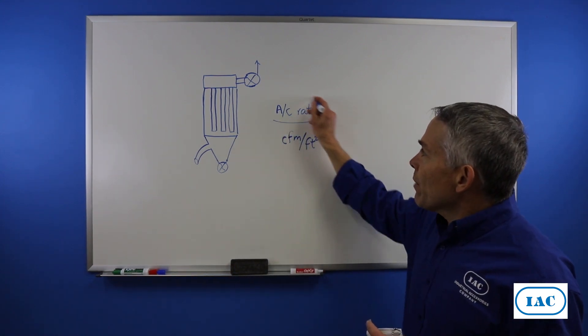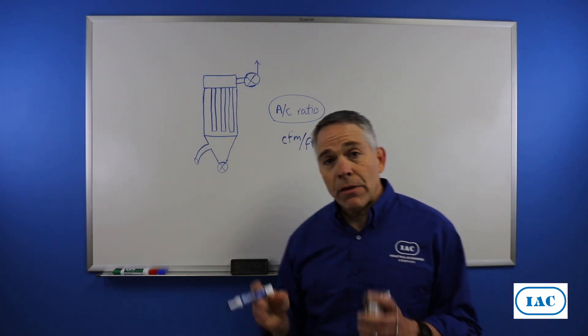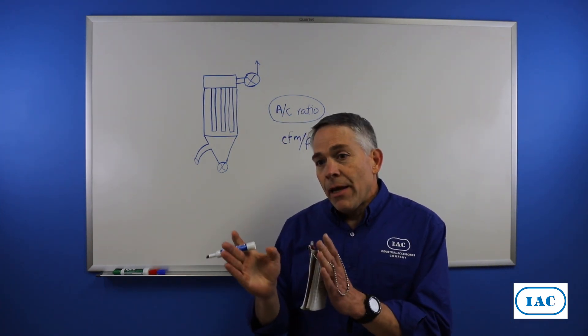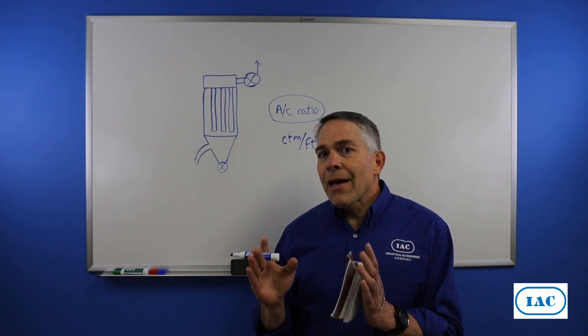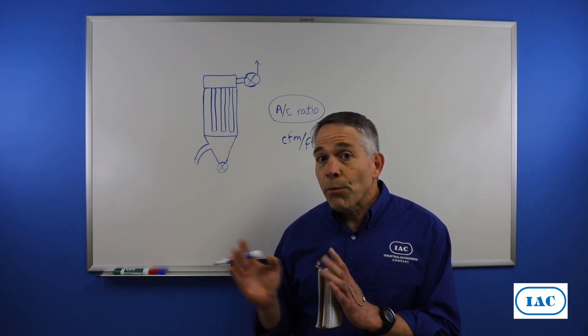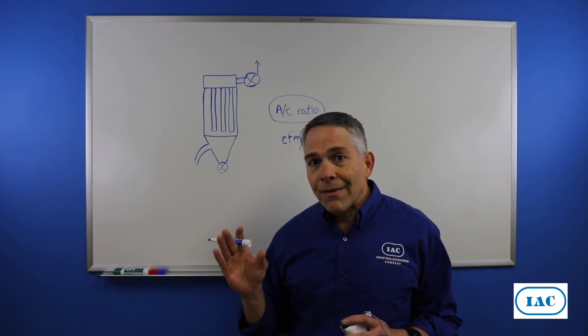Air-to-cloth ratio is the most important parameter in designing bag houses and that's usually what people look at. And yes, as a rule of thumb, the lower the better, but we need to keep an eye on the other velocity that's important in dust collector design.